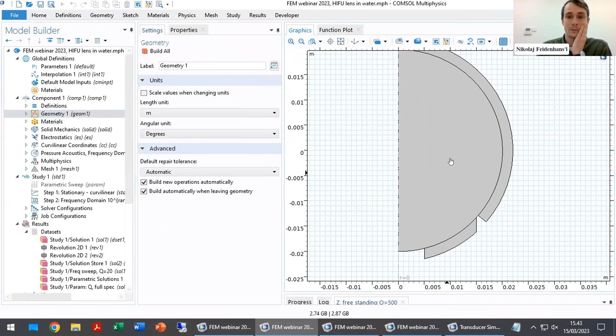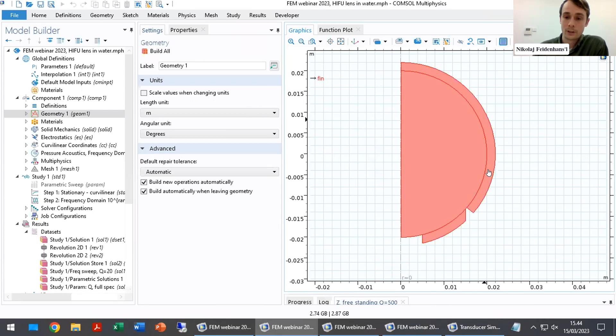We have the piezo like before on the bottom, then a big sphere of water. And then we have this layer on the outside, which is an absorbing layer, because if you don't put an absorbing layer, you will have a standing resonator where all the waves traveling from the transducer through the water will then be perfectly reflected at the boundary and go back, and you'll have some standing wave system, which doesn't at all compare to what you would probably have in reality. So by having an absorbing layer, you can simulate that all the energy just dissipates like it would in a water tank or in the body.